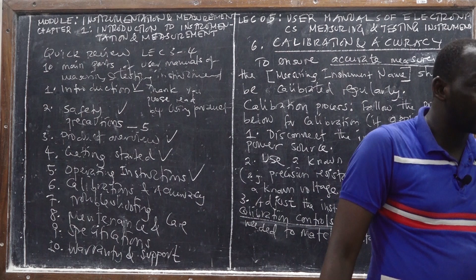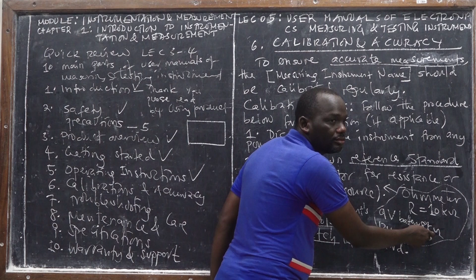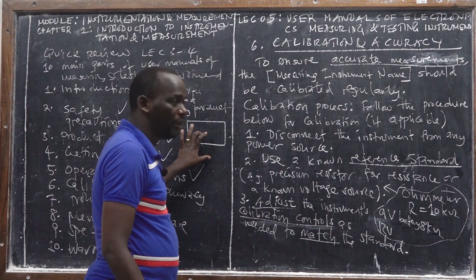Some of the measuring instruments can have special buttons for calibration. That's what we call the instrument calibration controls or knobs, adjusted as needed to match the standard. So you have to adjust it until you find that. How are you going to adjust? For instance, this is your instrument that you need to calibrate, maybe a multimeter. The standard reference resistor has a resistance of 10 kilo ohm, but before calibrating, when you measure it, the resistance reads 8 kilo ohm. So you have to adjust the control knobs of that multimeter until the display measures 10 kilo ohm, or 9.9 kilo ohm, or 10.1 kilo ohm.